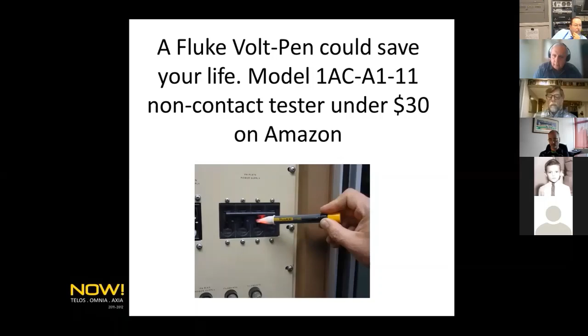A Fluke volt pen could save your life, and if you haven't invested the $30 for one, I really recommend it. They're available on Amazon, model number 1AC-A1-11. It's a non-contact tester that glows red near the proximity of AC circuits. So you may have flipped a breaker and thought it flipped but find out it didn't. Before you reach into the transmitter and start working, probe it with this to make sure there's no red indicator on the end, which would mean there's voltage present.